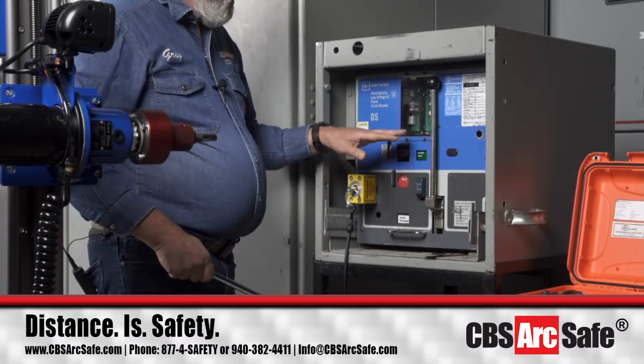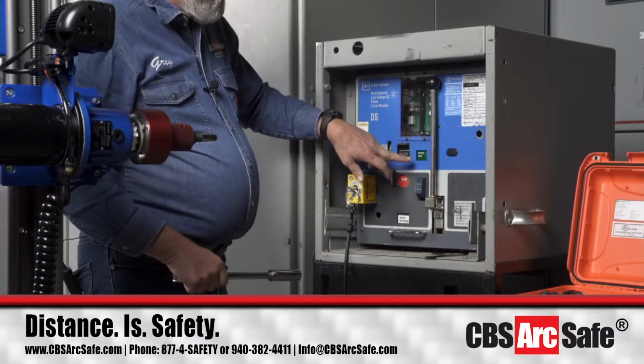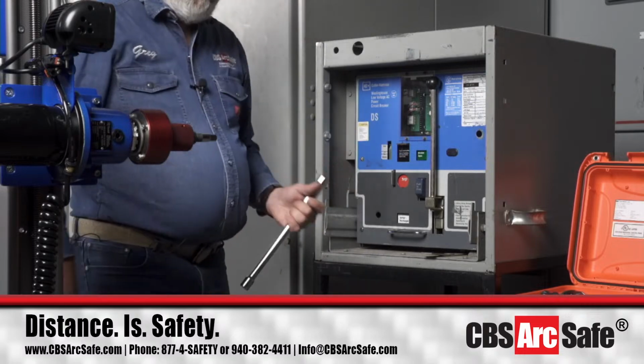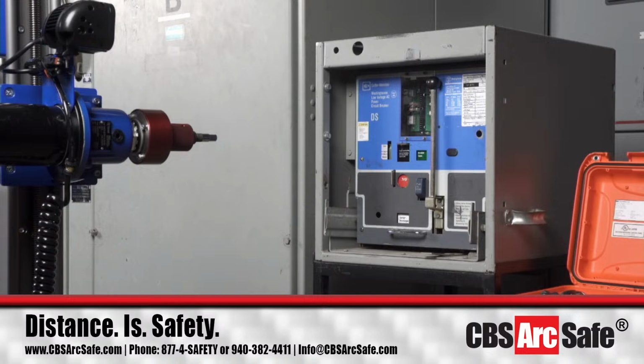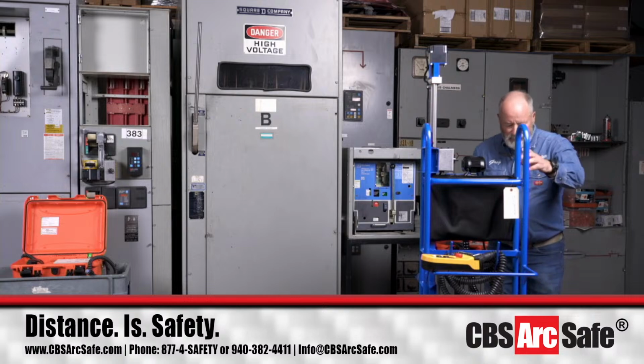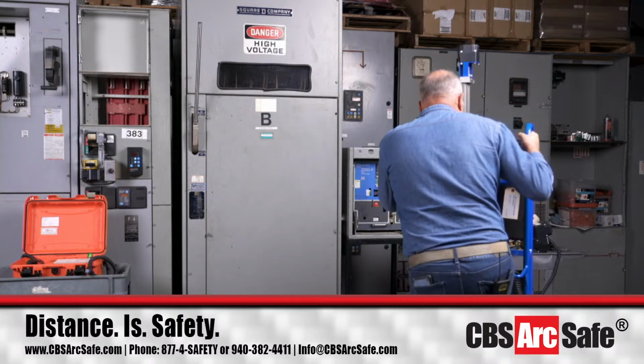Okay, so that's why we jog it back, but we don't leave it all bound tight, because this is actually tied into this. You would actually see if I did this that I could have a lot less force used for closing and opening the breaker when it's backed off just a little bit than when it's bound on tight. Now, the RSA 12A actually has a sort of funny history to it, because the vast majority of breakers that we run into with the DS are the manually operated ones. And a manually operated breaker, I'm going to move the RS1 out of the way here real quick, has a long arm on it versus a short arm.